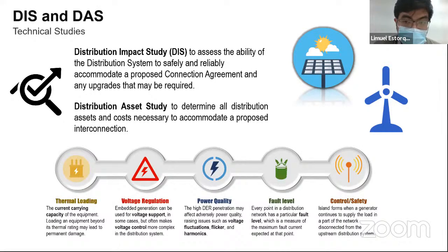First, it would have an impact on the thermal loading and power flows, both in normal state and during contingencies. Second, it also has an impact on the voltage control and voltage regulation, to ensure that the voltage can be properly maintained within the prescribed limits. Third, impact on power quality. So to check the quality of the voltage, frequency, and the current with the interconnection of the embedded generation in the system. High penetration of DERs or distributed generation may adversely affect the power quality, raising issues such as voltage fluctuations, flicker severity, and harmonics.